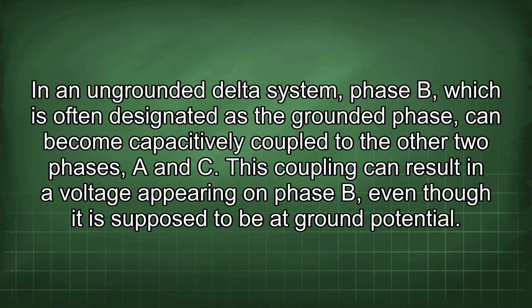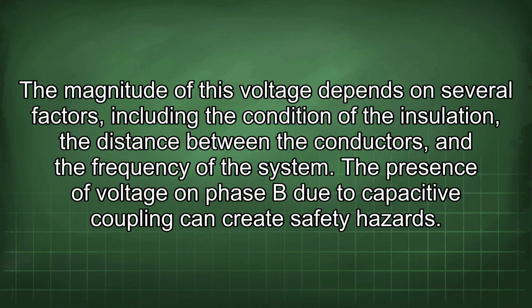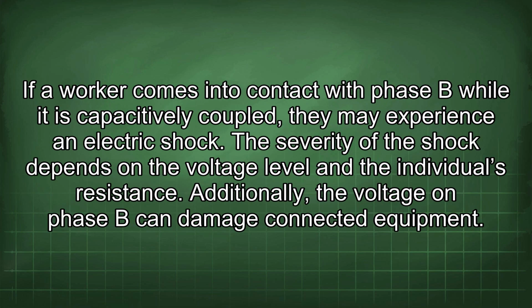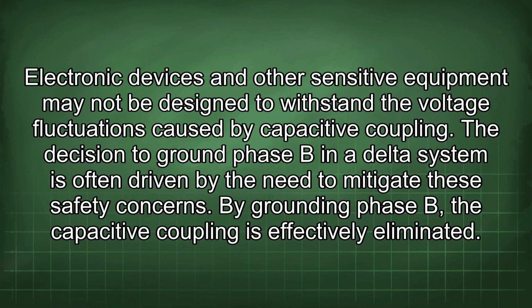In an ungrounded delta system, phase B, which is often designated as the grounded phase, can become capacitively coupled to the other two phases, A and C. This coupling can result in a voltage appearing on phase B, even though it is supposed to be at ground potential. The magnitude of this voltage depends on several factors, including the condition of the insulation, the distance between the conductors, and the frequency of the system. The presence of voltage on phase B due to capacitive coupling can create safety hazards. If a worker comes into contact with phase B while it is capacitively coupled, they may experience an electric shock. The severity of the shock depends on the voltage level and the individual's resistance. Additionally, the voltage on phase B can damage connected equipment. Electronic devices and other sensitive equipment may not be designed to withstand the voltage fluctuations caused by capacitive coupling.